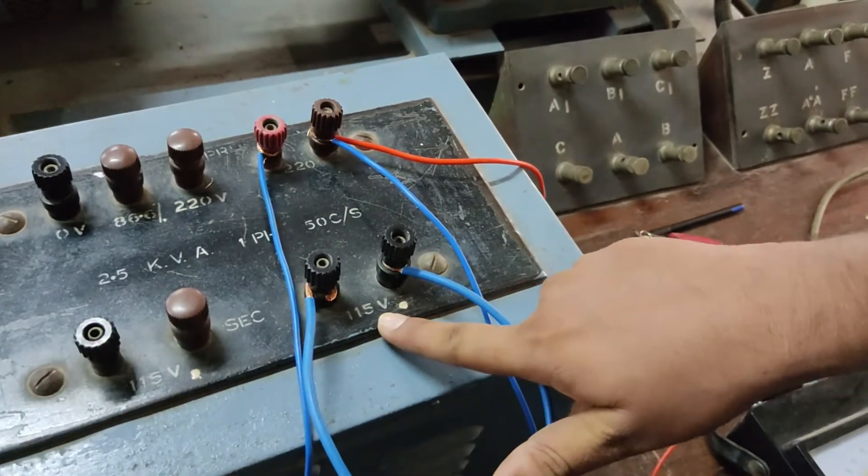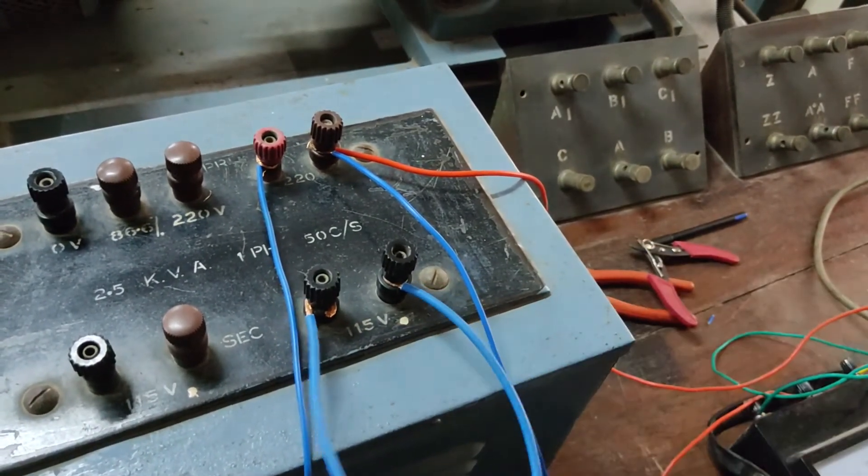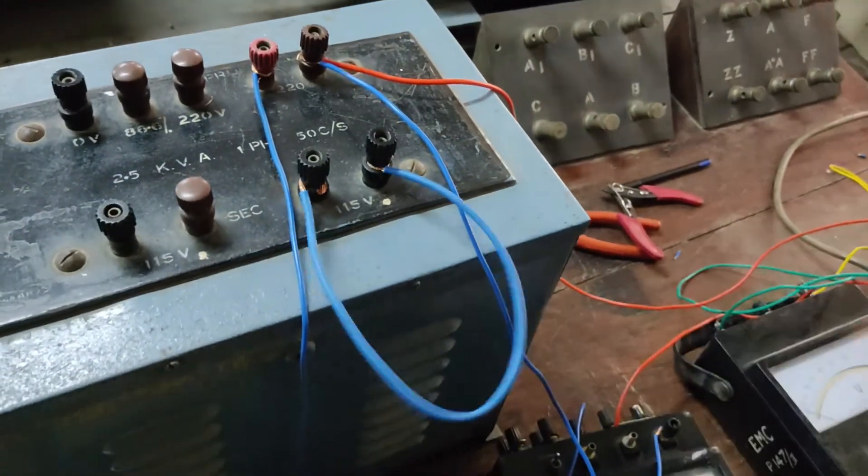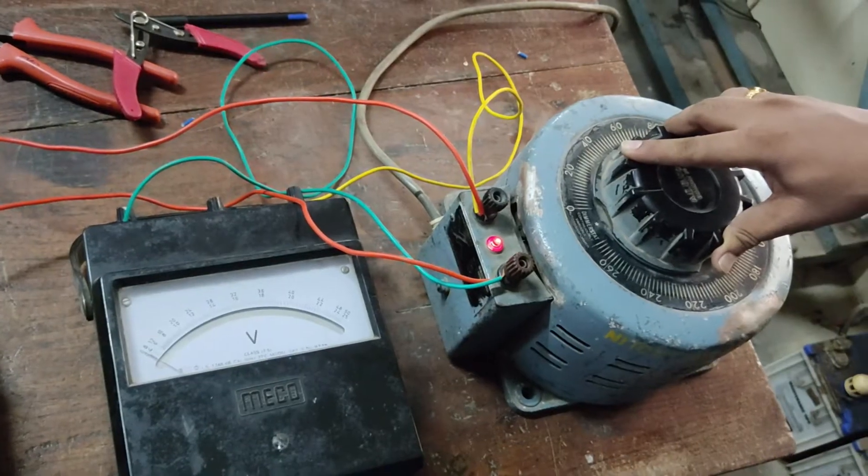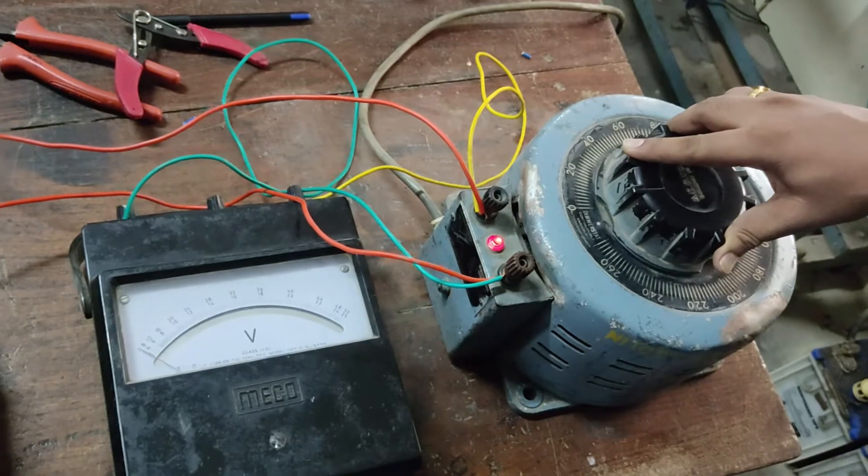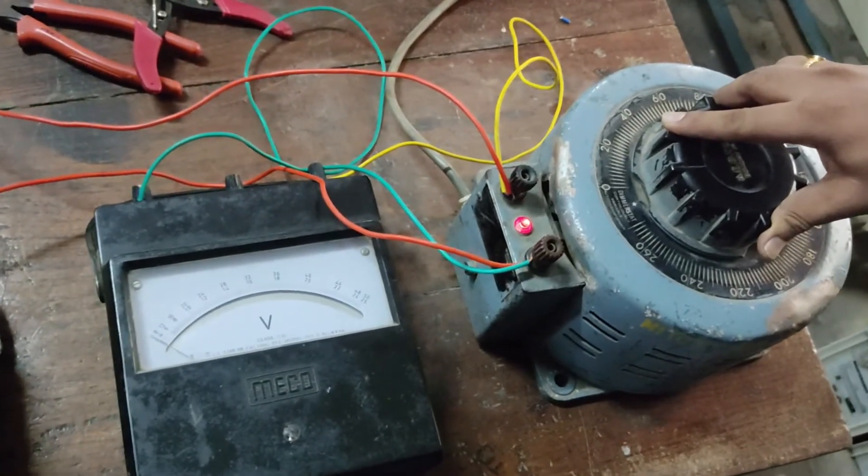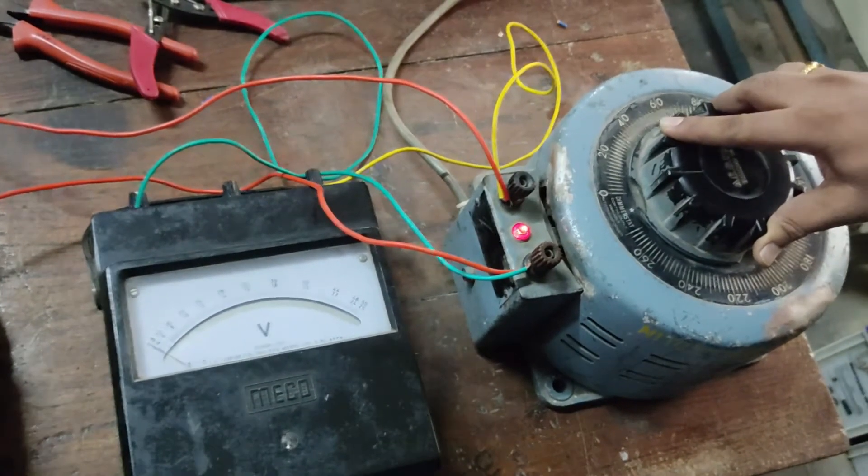The reduced voltage you have to apply to get full load current means only 8 to 12 percent of input voltage. You have to apply that and you'll get the deflection.